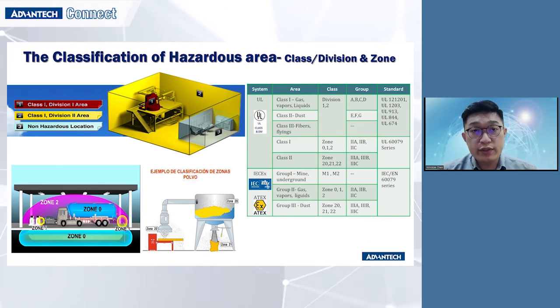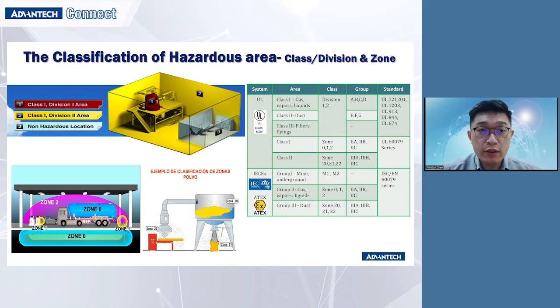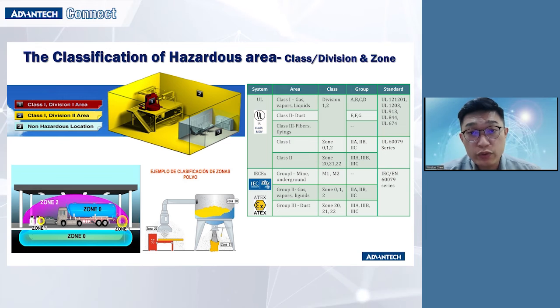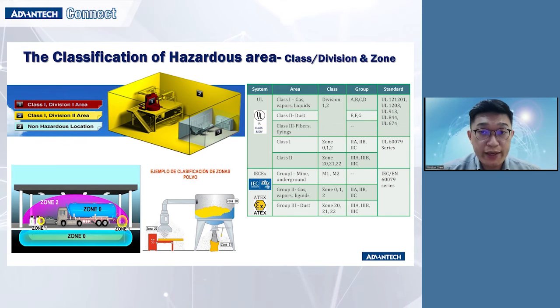Now let's look at the classification of hazardous areas. Sometimes we find a label marked C1D2, but what does it mean? The C means class, the D is division. Class 1 means gas, vapor, liquid, and class 2 means dust environment, and there's also class 3. Normally we apply C1, class 1, and D2, division 2. Division 2 means the explosive material sometimes or seldom exists in this area.